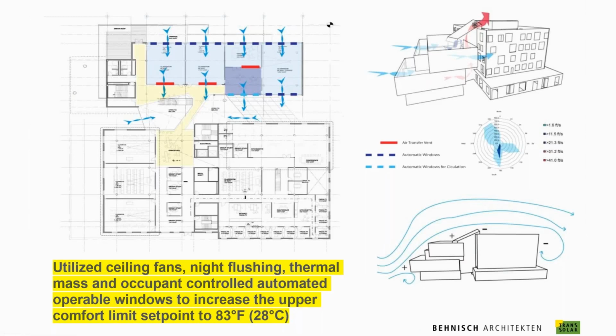So this is basically how it works. As I mentioned, there's only windows on the north side. This one on the edge actually doesn't go into the atrium on the top floor. It just uses cross ventilation. And that's, again, not uncommon for our buildings, but some spaces have a different strategy than the other spaces, just based on their architectural configuration. And that should be fine, especially since a space which is quite high up has a lot more wind pressure than a space that's low. So that's more driving force to get the natural ventilation through.